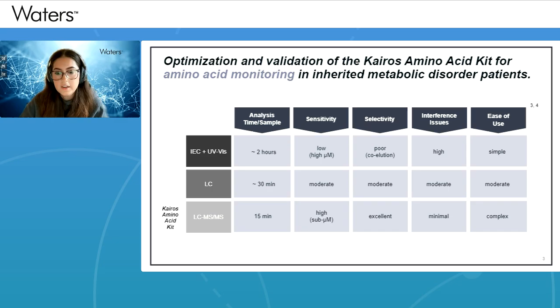And when we compare these, you can see why there is an obvious benefit to switching over. Starting with analysis time per sample, IEC methods can typically take upwards of 2 hours to analyze a single sample. LC averages around 30 minutes, and we are down to 15 minutes now, so it's much faster. In terms of sensitivity and selectivity as well, LC and MS methods are generally considered high or excellent, where IEC methods can deal with issues like coelution and have lower resolution. And interference issues are also less of a problem with an LC-MS-MS method. Conversely, on ease of use, it is a little bit more complicated to get an LC-MS-MS method started, but when you look at this all together, you can see that there's a clear benefit.